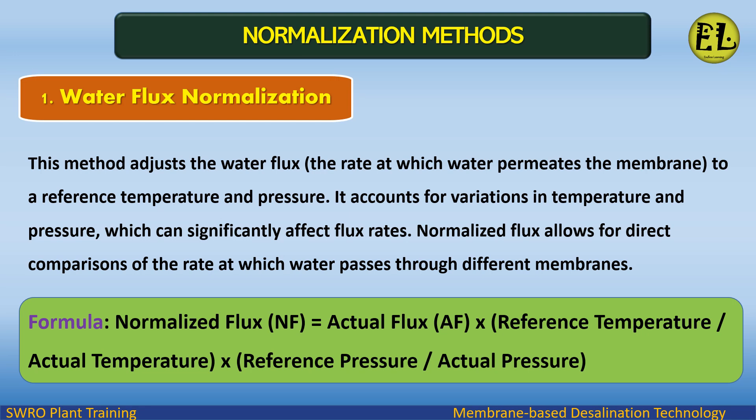Water flux normalization: this method adjusts the water flux — the rate at which water permeates the membrane — to a reference temperature and pressure. It accounts for variations in temperature and pressure, which can significantly affect flux rates. The formula is: Normalized Flux (NF) = Actual Flux (AF) × (Reference Temperature / Actual Temperature) × (Reference Pressure / Actual Pressure).